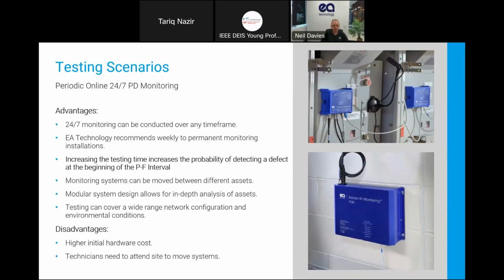Okay. So the next one is moving up to using a monitor, but on a periodic basis. When I first started working at EA Technology, which is way back in 1996, this is one of the things that we would always recommend to the network operators that we worked with: we would look for testing maybe every 2 to 4 years. We would look for putting a monitor onto a switchboard for a period of, say, 1 week. Now, what that does is it does improve the probability of detecting a defect.